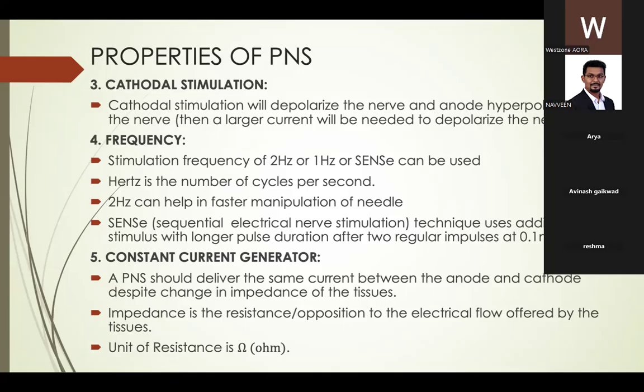And this PNS must have a constant current generator. A PNS should deliver the same current between the anode and the cathode despite changes in impedance. Impedance is the resistance or opposition to the electrical flow offered by the tissues, and the unit of resistance is the ohm.